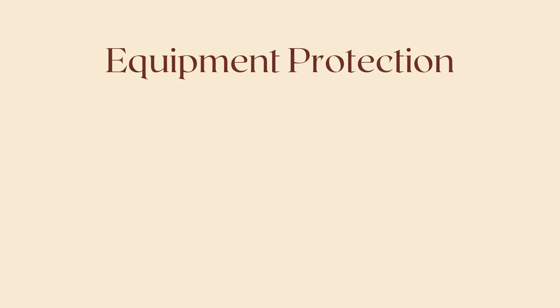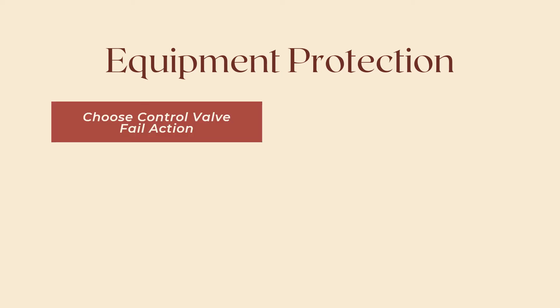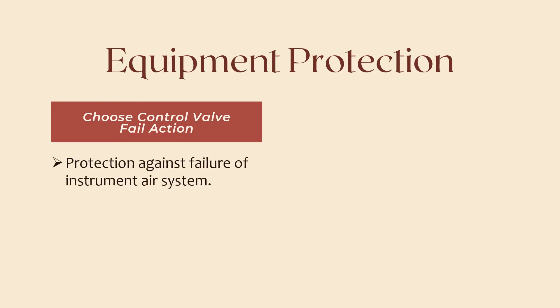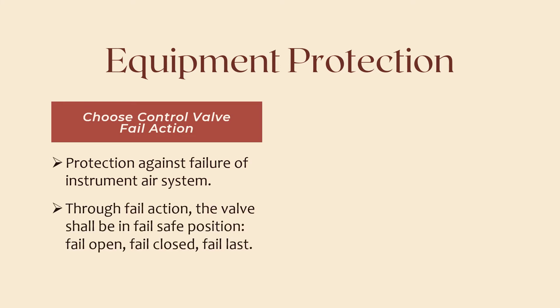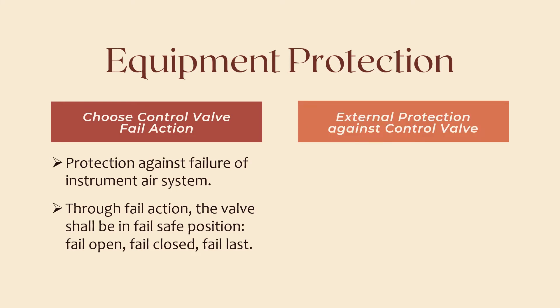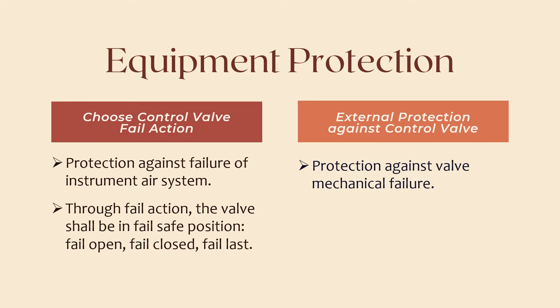So if we want to ensure that the plant shall not have any safety issue if the control valve failed, we should first make sure that instrument air failure won't create a safety issue due to accidental opening or closing of a control valve. We should choose the correct valve fail action, whether it can be fail open, fail closed, or fail in last position. But still there is a probability that the control valve stem is mechanically stuck in a position where it can cause a safety issue, which is why we would need external protection against valve mechanical failure.